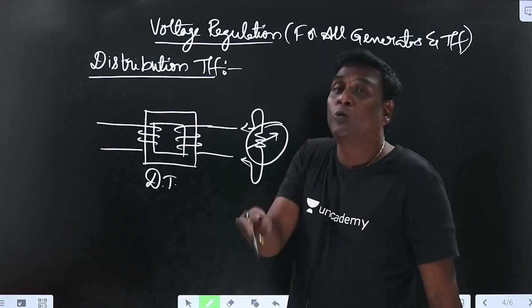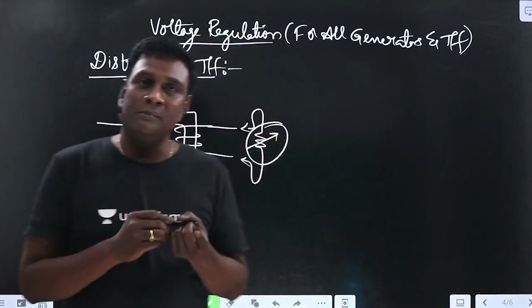So the point here is that terminal voltage can be maintained independent of loading conditions in a power transformer by varying taps, and in an alternator by varying field current. But in a distribution transformer, terminal voltages are going to vary directly. So we understood two points now. First, my loading condition is going to vary in a distribution transformer. It may work at full load, at half load, at low load, or at 3/4 full load.